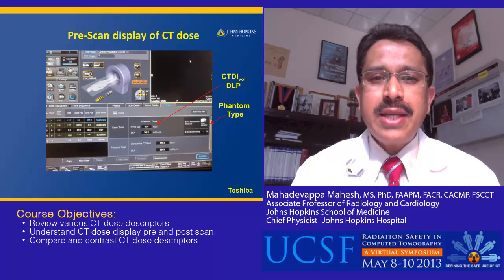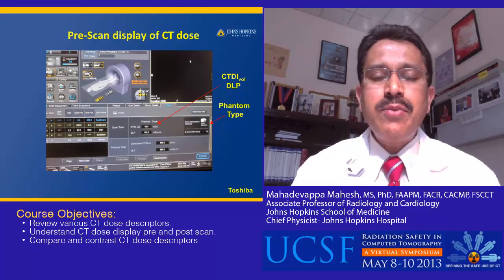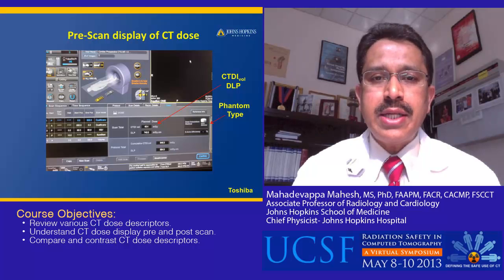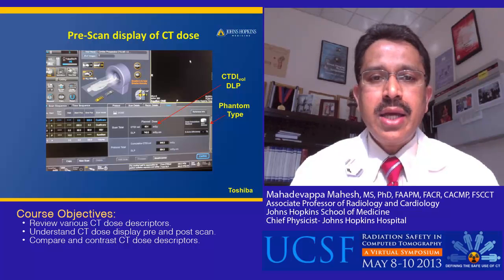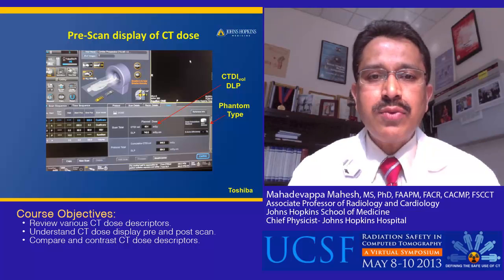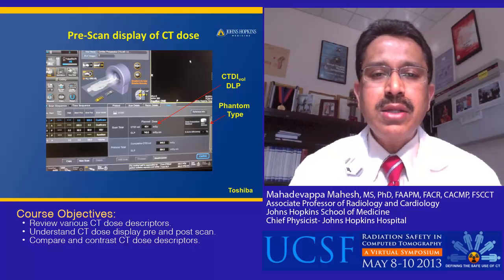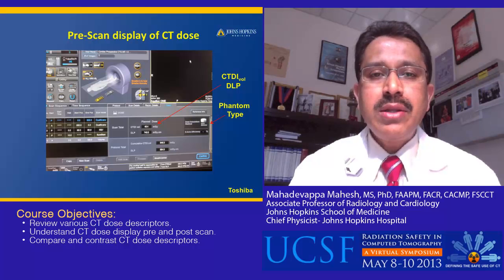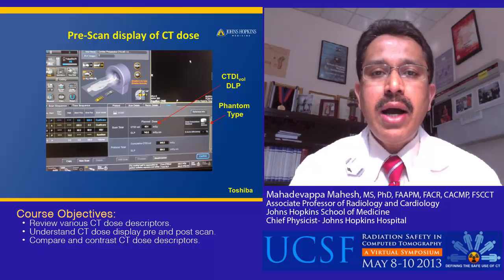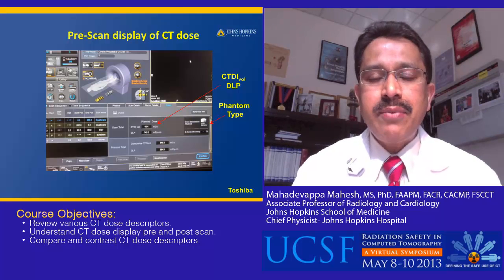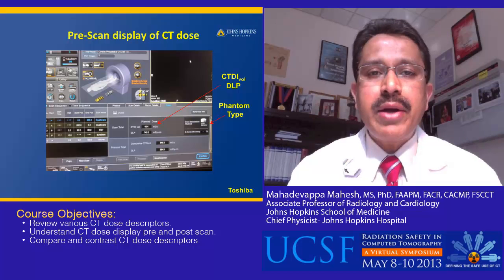This slide shows a pre-scan display from a different manufacturer. Along with the CTDIvol, there is also a planned DLP displayed on this screen. The use of a pre-scan display is that for a technologist setting up a scan, if he or she knows the general range of the CTDIvol for a particular CT protocol, they can indirectly verify whether the technique is correct. If the technique is accidentally changed — such as the kV, mA, or pitch value — this will immediately be reflected as a very high or low CTDIvol.